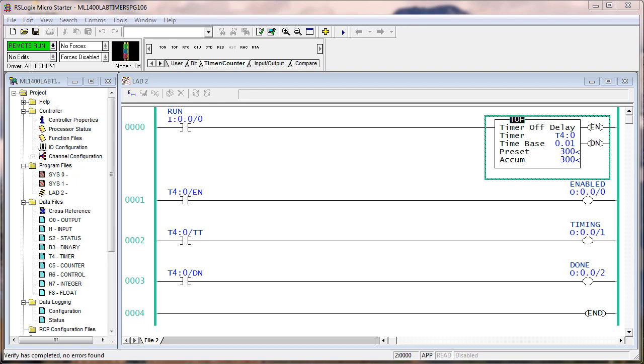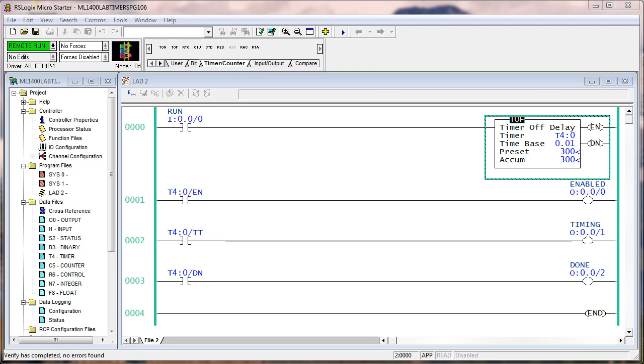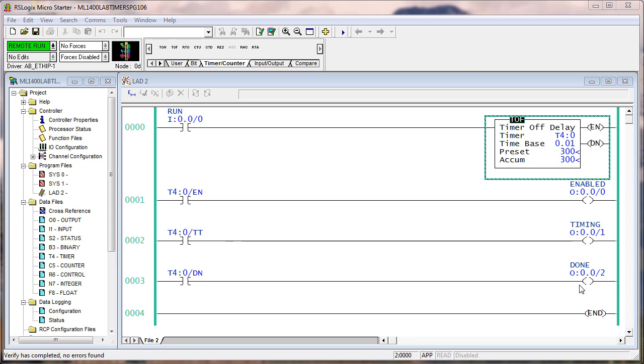The done bit went off three seconds after the run went off. So the whole relationship here with the TOF is between the conditions that enable the timer and the delay before the done bit goes off. When I say the done bit, I mean this bit right here, okay, in rung three.